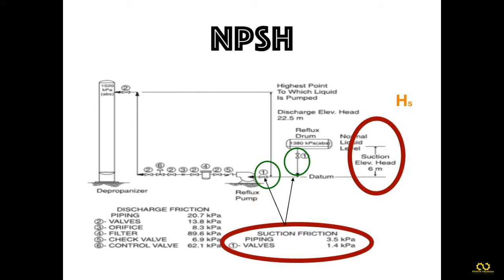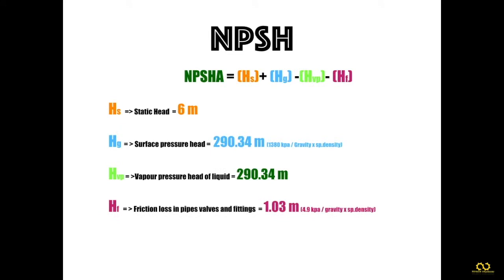To identify net positive suction head, the head is measured in meters or feet. Next is the surface pressure of the liquid, given as 1380 kilopascals. You should consider the suction surface pressure, not discharge pressure, as cavitation only concerns the suction side. This should be converted to meters. The given vapor pressure is also 1380 kilopascals. Normally, engineers calculate vapor pressure using the inlet temperature.